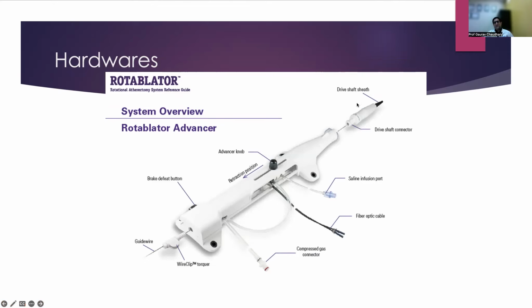In the distal part, it has a drive shaft and a drive shaft connector, and this is the body of the advancer, and there are three ports. One is for saline; there should be continuous saline infusion. One is the fiber optic cable, which is connected to the tachometer, which measures the speed of the rotablation burr. And the third one is the compressed gas connector, through which the pneumatic pressure rotates this burr. In the distal part, we have a brake defeat button, and we also have an exit for the guide wire, the rotor wire, and over this we can apply a wire clip torque.